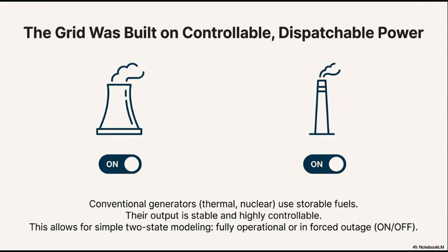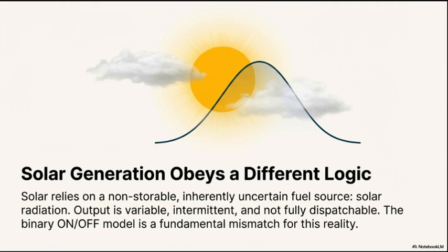Exactly. This transfer process is called convolution. Think of the original predictable load curve, say the known peak demand at 6 p.m. Convolution takes the generator's outage capacity distribution, the multi-state probabilities for solar, the two-state probability for gas, and mathematically smears that risk across the entire load profile. So the resulting output isn't just the load, it's the load plus the likelihood that you won't be able to serve that load because of generator failures. Precisely. That resulting curve is the equivalent load duration curve, ELDC. The ELDC is the single probabilistic point of truth that incorporates all uncertainties across the entire system.